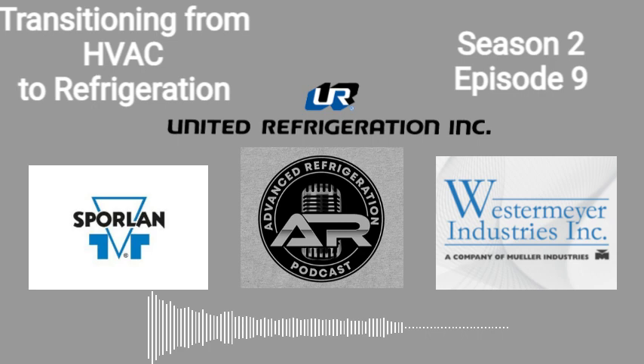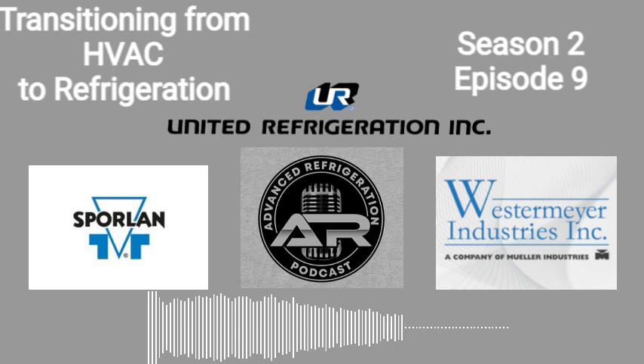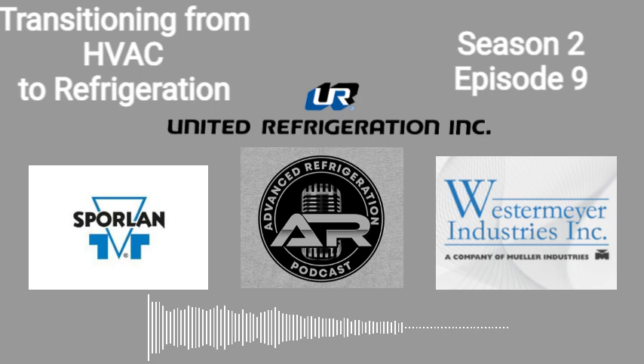So all bigger valves, obviously, you have more flow, so you're not going to be able to get a screen in there when you have a 5/8 or 1/2 inch inlet. With those valves, for example, big box retailers like Sam's and Costco have POS freezers. Those are all big valves. Sam's Club sometimes you get serviceable valves, but Costco, for example, has an 8-ton valve inside the freezer. There is an internal screen in there, but it's that ballpoint mesh screen. So you'd have to unbraze it.